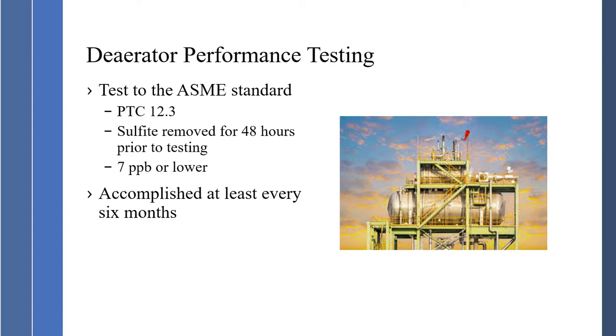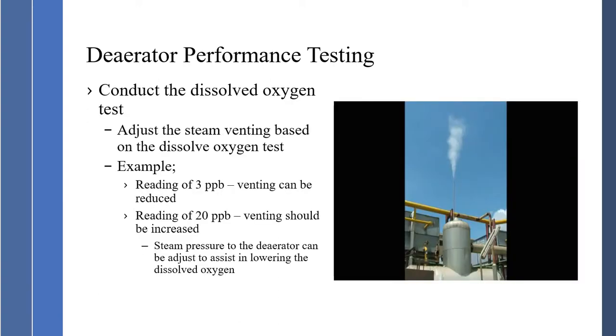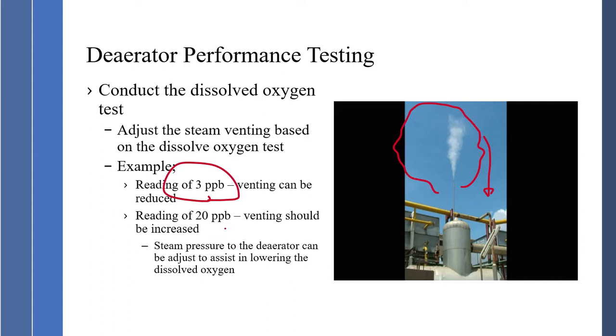That will tell you the deaerator performance. When conducting the dissolved oxygen test, we can adjust the steam venting based on the results. For example, at 3 parts per billion, I can reduce the amount of venting — I don't want to go over 5 parts per billion, and definitely not over 7 parts per billion, but I do not want unnecessary energy loss. If I get a reading of 20 parts per billion, venting should be increased, because that will help assist in getting rid of the non-condensable gases.